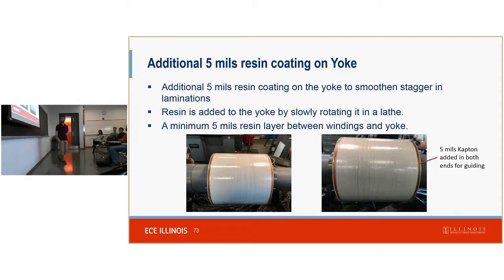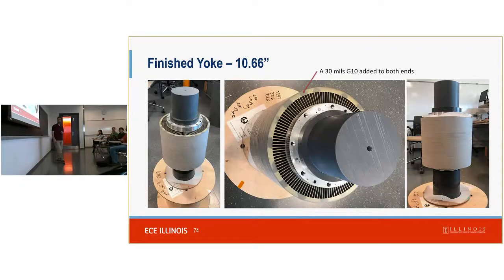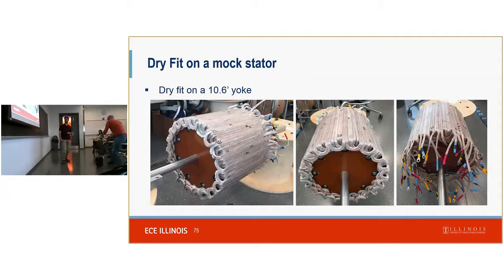And then a thin layer was applied, and a layer just thick enough to fill in the gaps was applied, and then an additional 5/1000ths of an inch was applied to the outside for the electrical insulation. So this is the finished yoke with that ceramic-filled resin applied.